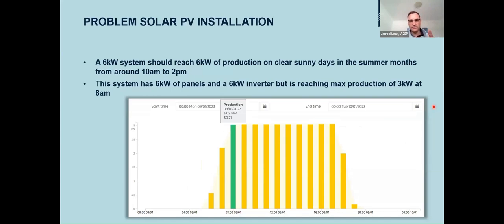Here's a case of that happening: a system with 6 kilowatts of solar panels, 6 kilowatts of inverter, and on a very nice sunny day it's still only achieving 3 kilowatts of output. This isn't uncommon - it happens quite often, and we believe it's a mistake in how the inverter was connected. The production comes up quickly, already reaching 3 kilowatts by 8am, so it looks like the panels are all well connected into the inverter, but something's wrong with how the inverter is set up or connected, so it's only putting out 3 kilowatts - missing a lot of energy production. So wait for a sunny day, check that, and make sure the energy production in kilowatts is very close to what was specified.